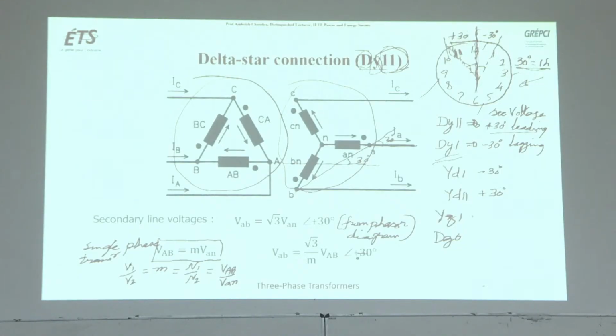If you say DY1, again on the primary side you have delta winding, on the secondary side you have star winding. 1 means the secondary voltage is lagging by 30 degrees with respect to the primary. So if we say YD1 transformer, primary is star, secondary is delta, and the secondary voltage is lagging by 30 degrees. 1 is the lagging here, right? This is the reference, this is the 1. YD11, 30 degrees leading. Then you may have YZ1, that is primary star connected, secondary zigzag, and 30 degrees lagging. DZ0. So these things are there.